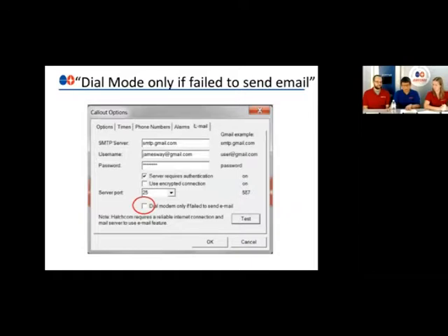So this allows the user to see which machine and alarm has been activated, but still get an alarm notification by phone call in case the email is delayed or lost. And most of all, email callout provides more detailed information. So you will not be wondering what's going on with your hatchery once you receive the phone call, because the email will confirm what's the exact problem going on in the hatchery. So you will set 2 call entries for the same person. The first one to send an email. The second one is to place a phone call. So that concludes the call out.